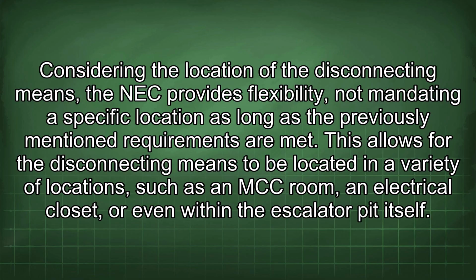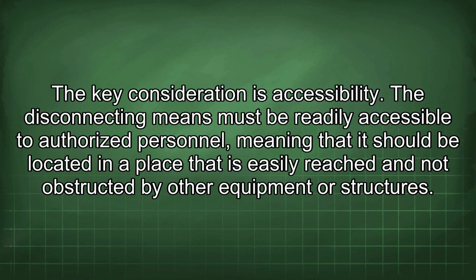This allows for the disconnecting means to be located in a variety of locations, such as an MCC room, an electrical closet, or even within the escalator pit itself. The key consideration is accessibility. The disconnecting means must be readily accessible to authorized personnel, meaning that it should be located in a place that is easily reached and not obstructed by other equipment or structures.